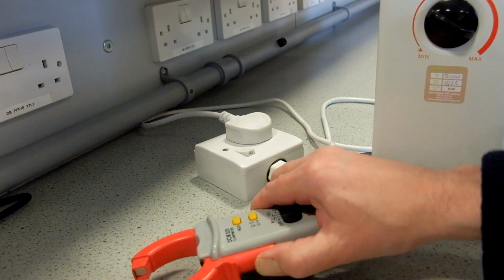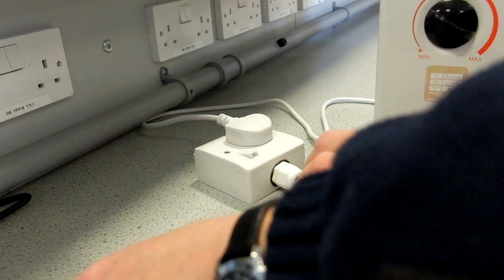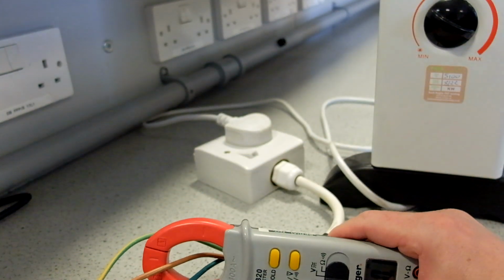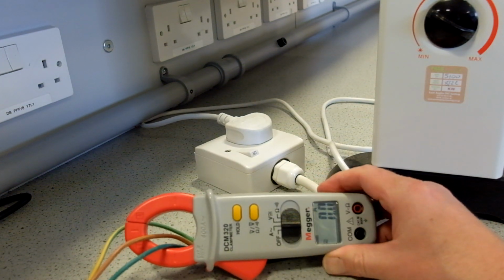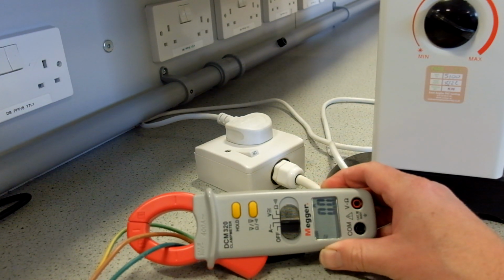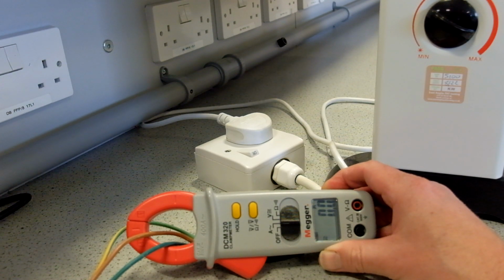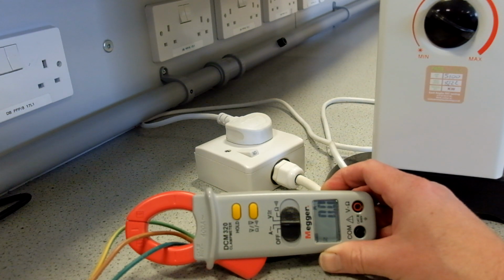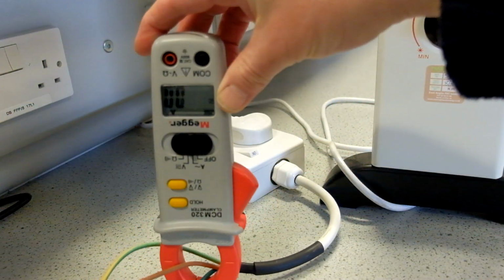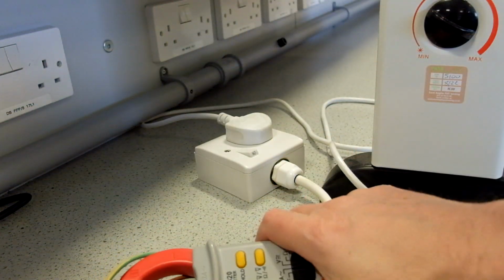It's only there to provide fault current path. If we measure current around both the live and the neutral cables together, what do we get? We're measuring 0 amps coming out. There is a little bit flicking there to 0.1, which is a little bit surprising. We would expect that the current going through the neutral, the current going through the live are exactly the same.